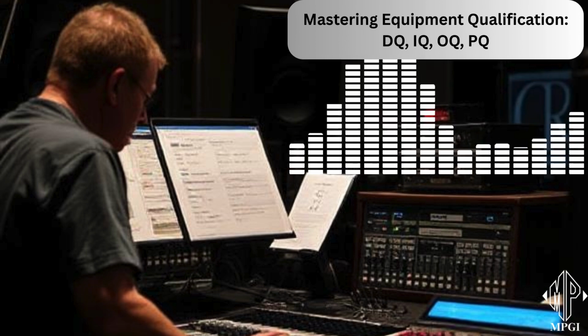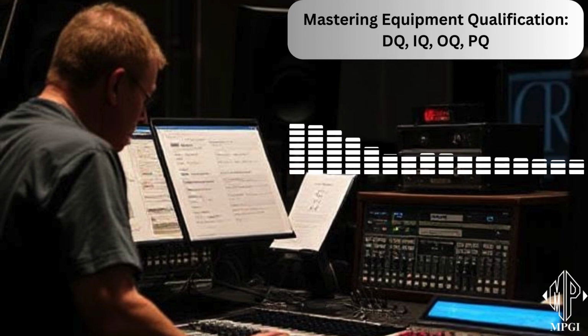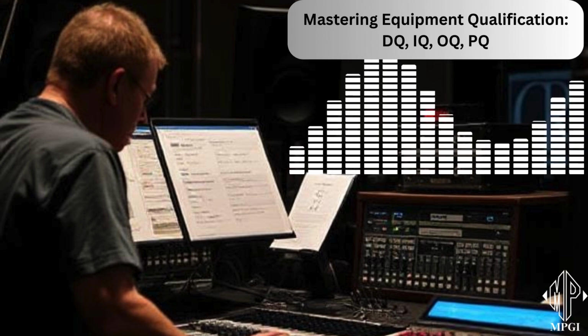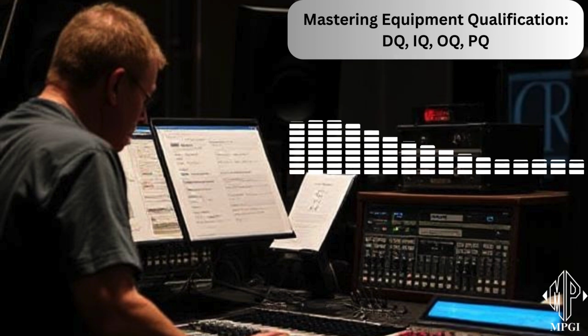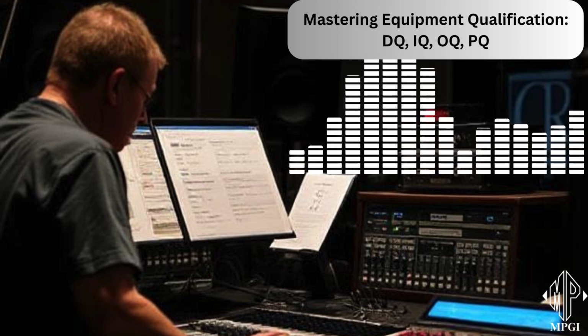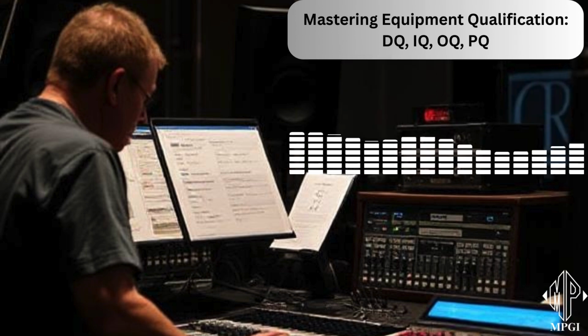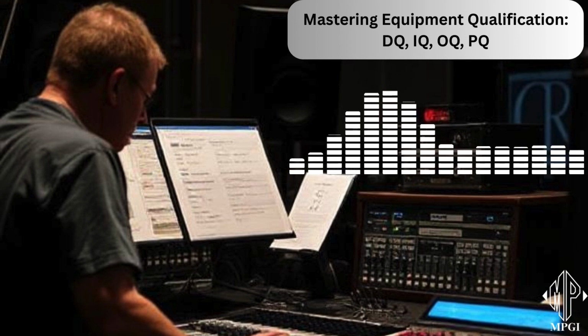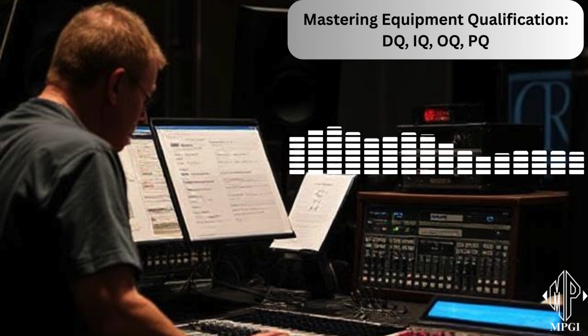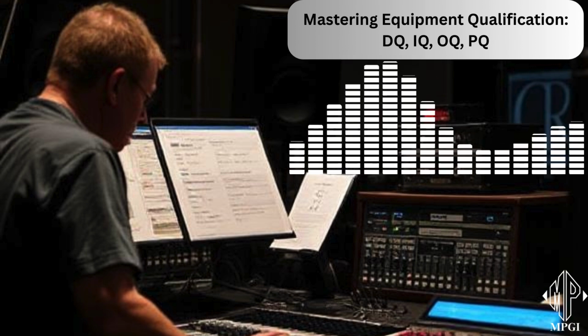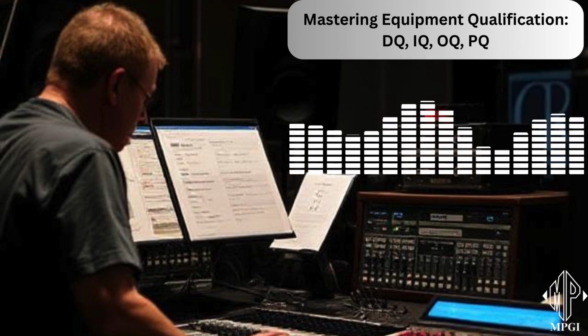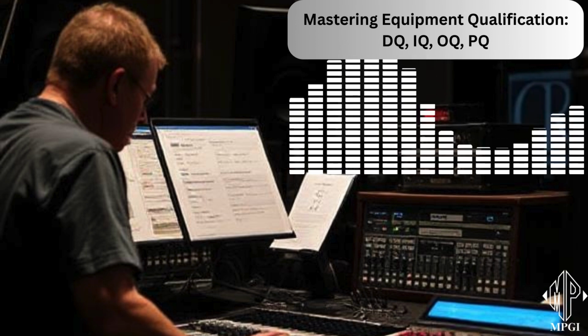Can you give us some examples of what a PQ might look like for different equipment? Sure. Let's say you have a liquid filling machine. Like for filling bottles of cough syrup or something. Exactly. A PQ test might involve running the machine with the actual product at various speeds, checking if it consistently fills the bottles to the correct volume. Making sure every bottle gets the right dose. Right. For a sterilizer, like an autoclave, PQ would involve running it with actual production-sized batches and making sure it consistently hits those critical sterilization parameters: temperature, pressure, and time.